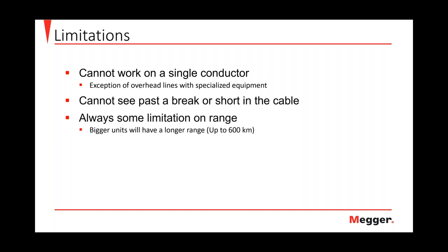We're always going to have some limitation on range, even though the range on these units is typically pretty good. Some of the bigger units can get up to around 600 kilometers for effective visibility. But it cannot find a pinhole fault by itself. So we need an integrated unit, or we need a unit that works in conjunction with a surge pulse generator in order to find pinhole faults.